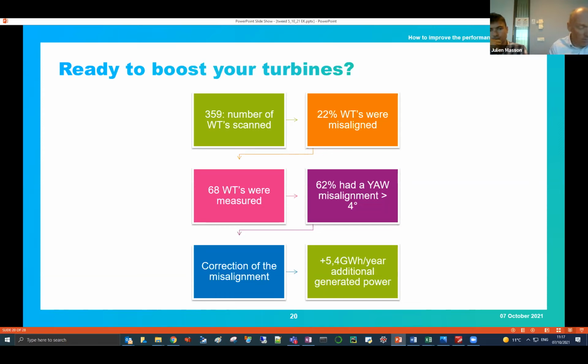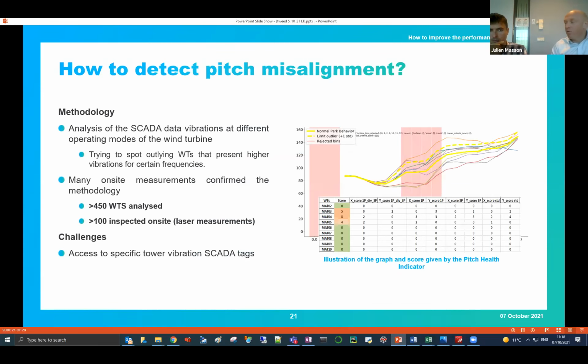If you remember the graph that was previously shown by Julien, you remember that for 4 or 5 degrees misalignment, we have approximately 2% of production losses. That means if we perform the correction of this misalignment, we save more than 5.4 gigawatt hours a year of power for the owners of the wind farm. That's of course a huge figure, but you see directly that it is interesting to perform this yaw scan as a first step. Now, Julien, maybe you can.